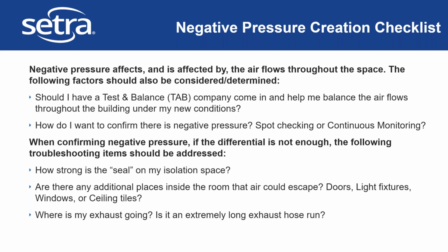Negative pressure is affected by, and affects, the airflows throughout your space, not just in that standalone area where you're using it. You're exhausting air out, and therefore pulling more air into the space. So it's important to consider how incorporating negative pressure would affect the space overall.